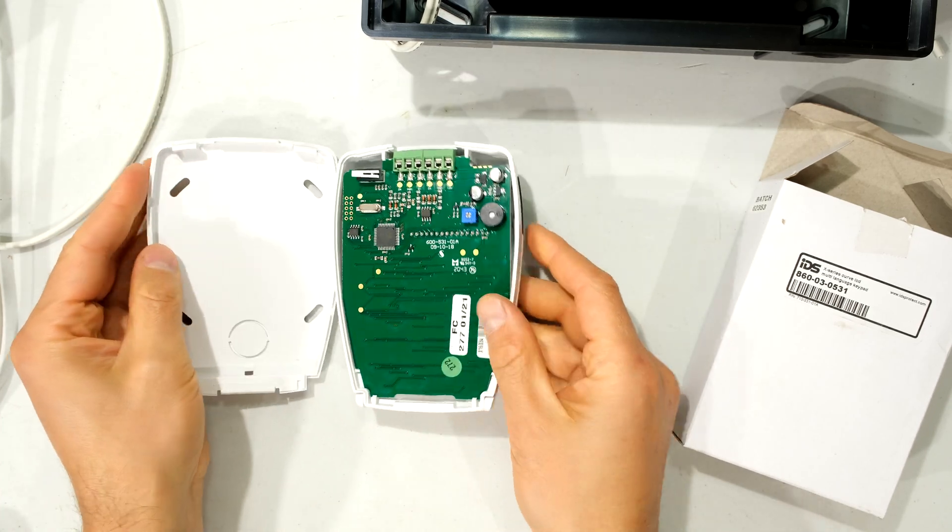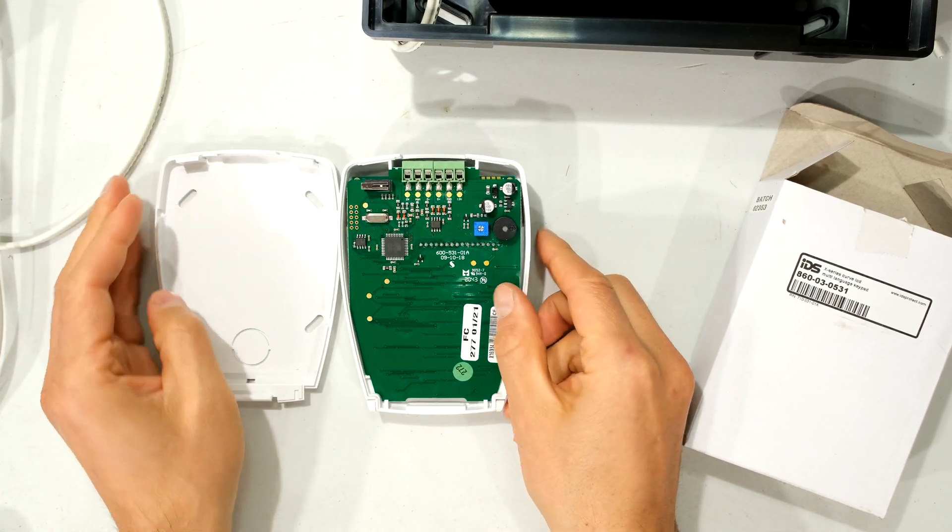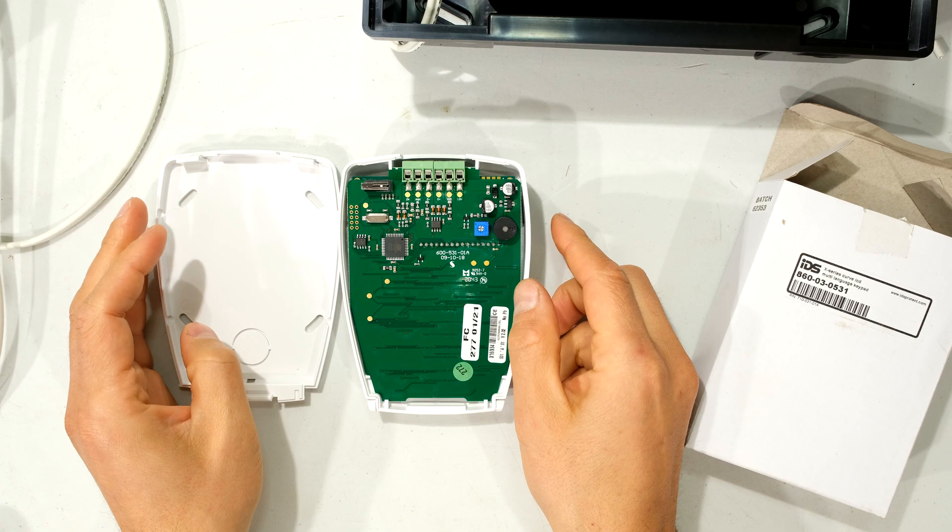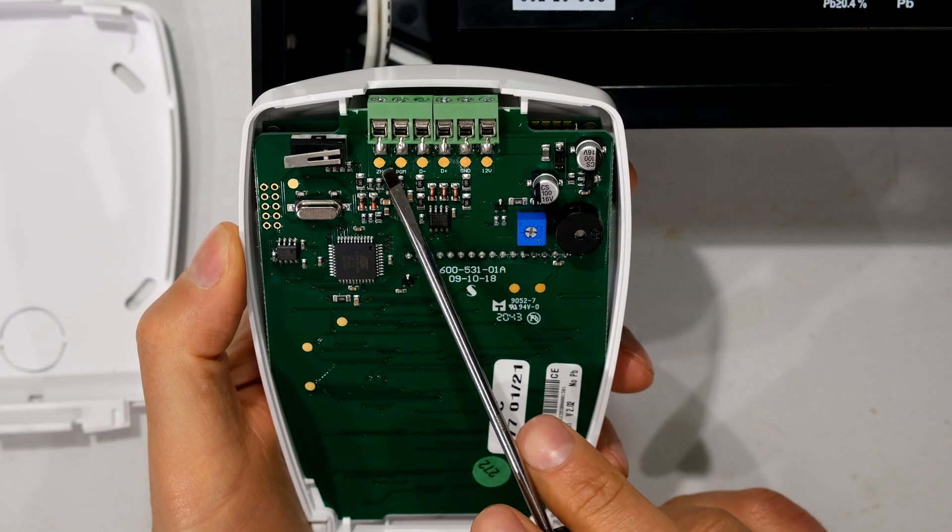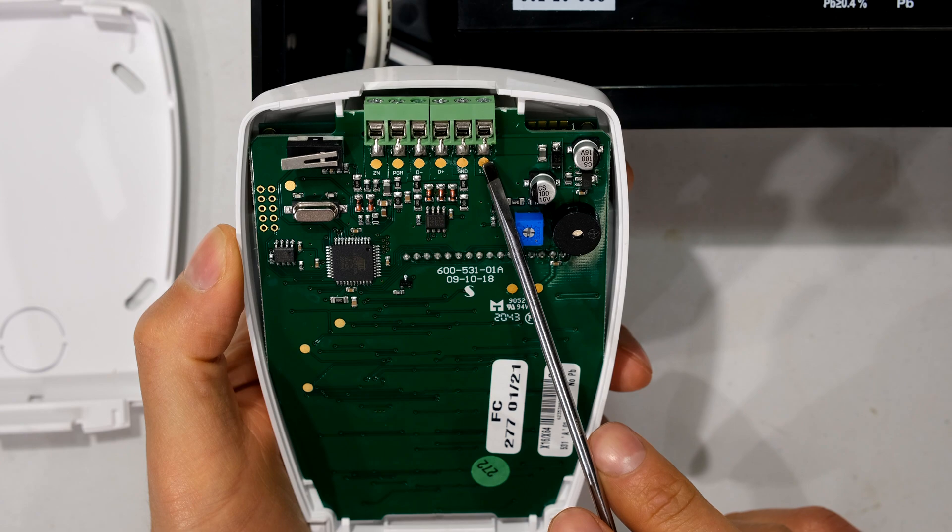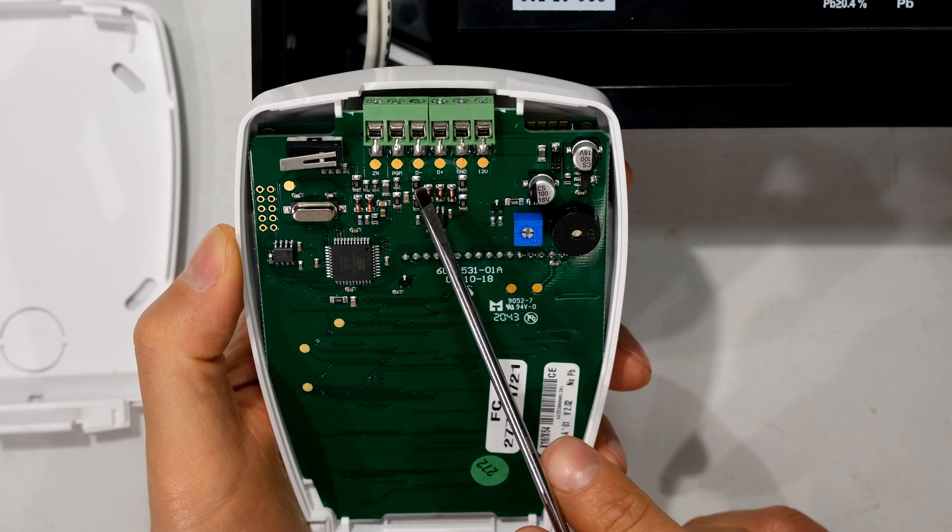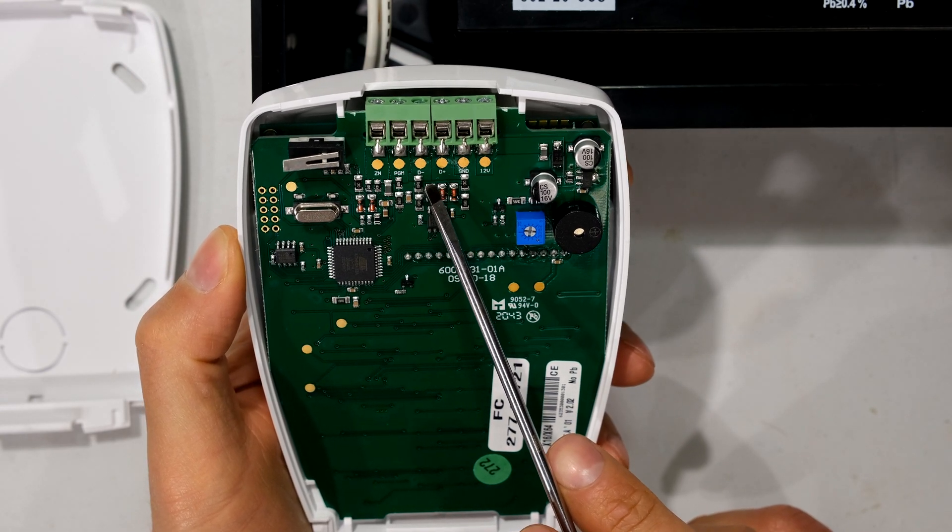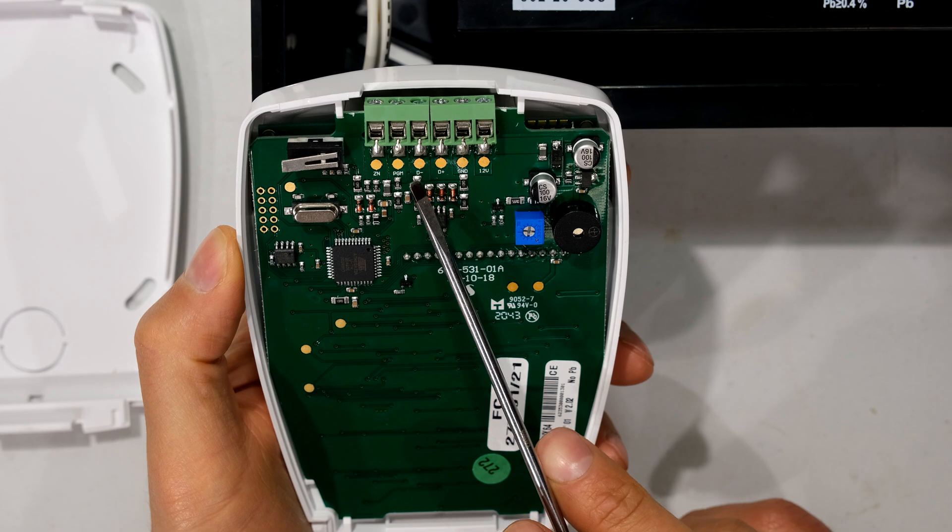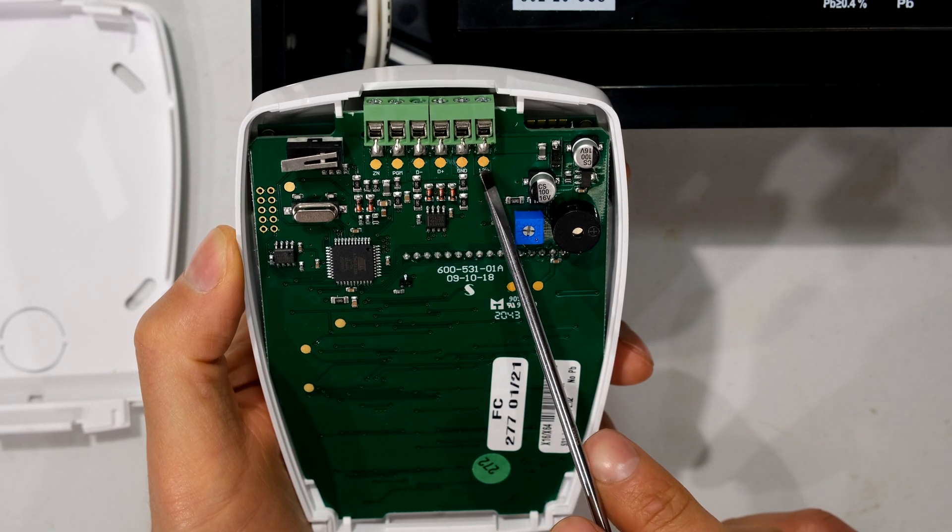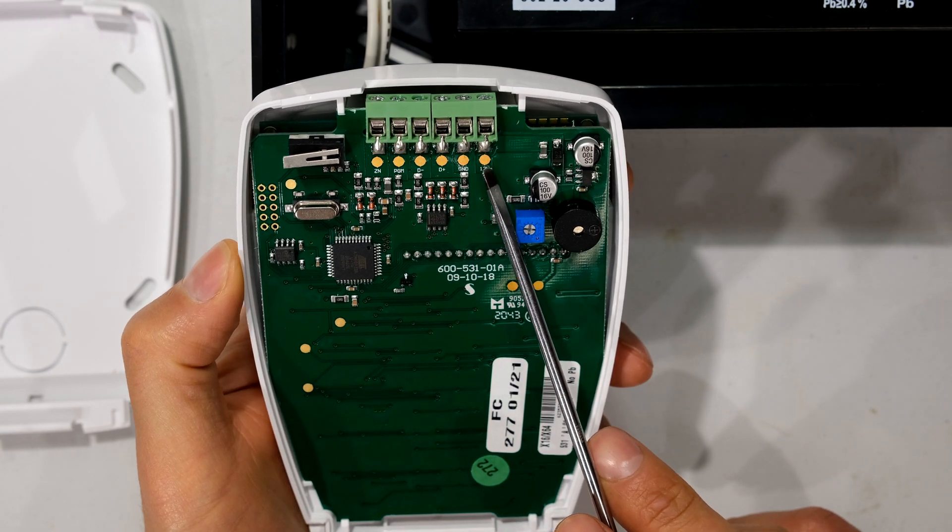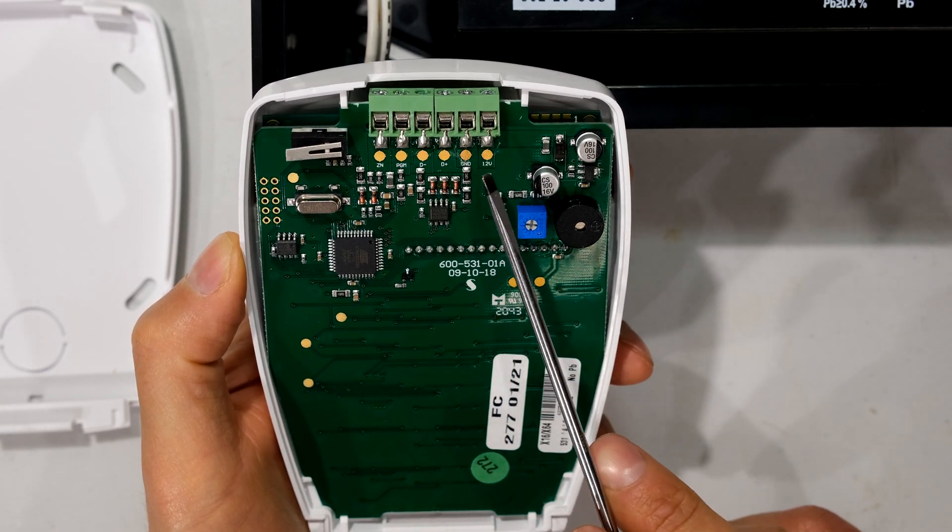And all I need to do is now get my comms cable, which is going to be a minimum of a four wire. You will see there are six connectors here. Now the ones for the keypad to connect to the main board are these four: D minus, D plus, ground, and 12 volts. So we only need to use the four out of the six.